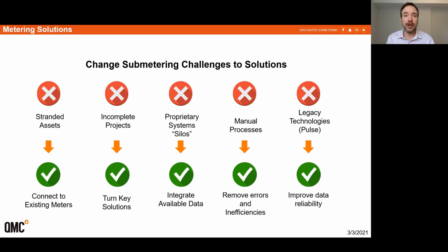First, stranded assets—that's where a meter system has been deployed and the meter hardware is no longer usable, either because it's older technology or was never set up for remote communications. Instead of leaving that equipment inaccessible, we connect to it using module adds to the meter to get an output, whether Modbus or BACnet, and install a universal data logger to collect that data.